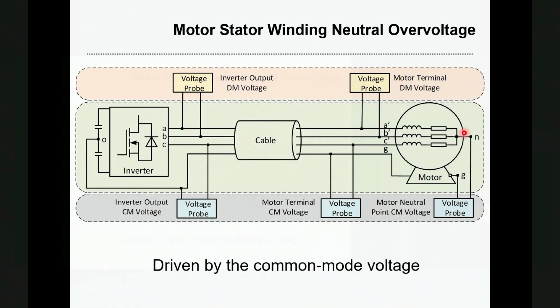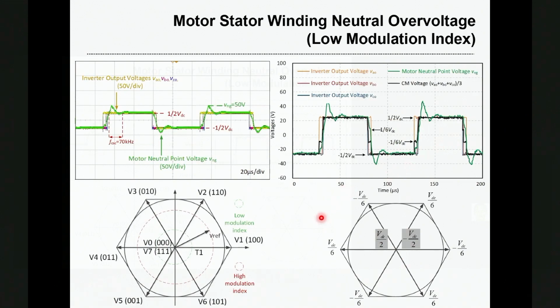And then let's look at the motor stator winding neutral point overvoltage. This is a common mode type of overvoltage because of the impedance mismatch at the motor stator neutral. And we can analyze this using the space vector diagram. Basically, if you know the two-level converter modulation, you will know there are 8 space vectors, and there will be corresponding common mode voltage associated with these space vectors.